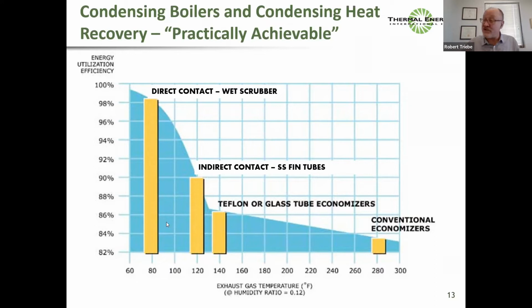Of course, the worst heat exchanger in this graph could achieve what the most efficient heat exchanger achieves if we make it absurdly large. So these are practically achievable efficiencies with different technologies. And as we know, I'm in Fahrenheit now, so the y-axis is your efficiency, thermal efficiency, boiler efficiency, which means if your exhaust gas is the same temperature as your combustion air, I've got combustion air coming in at 60 F. If my flue gas is 60 F, I'm 100% efficient thermally because I put in 100 units of fuel into that combustion air, I heated it up, and I cooled it down to the temperature it started at.